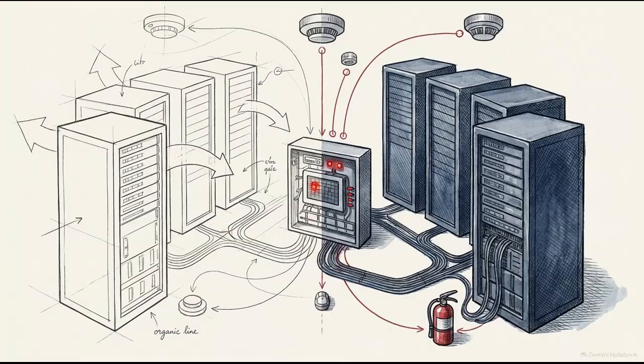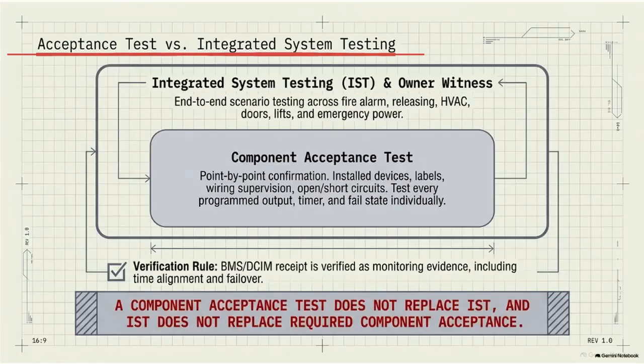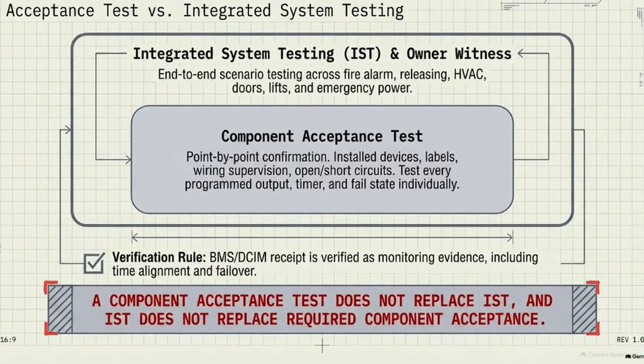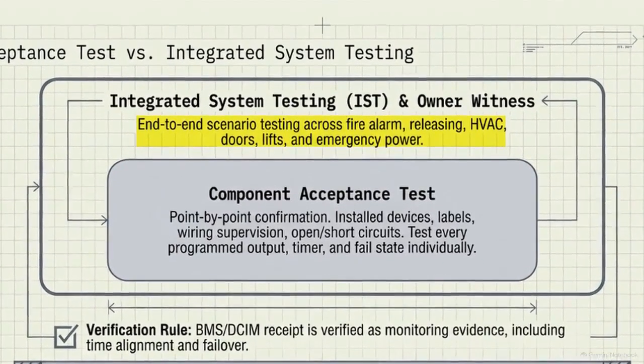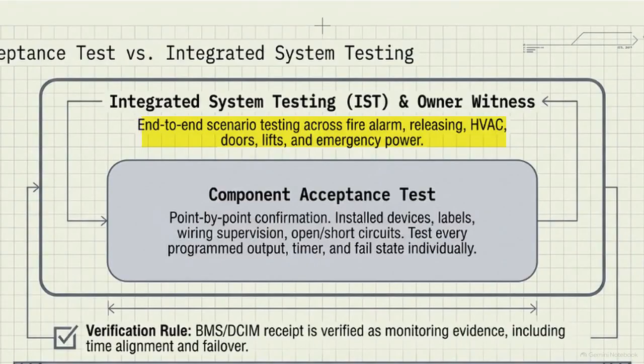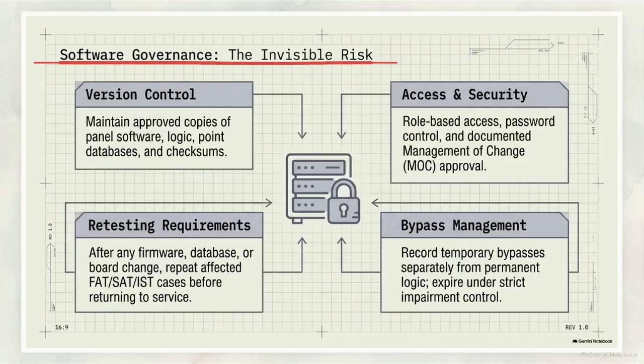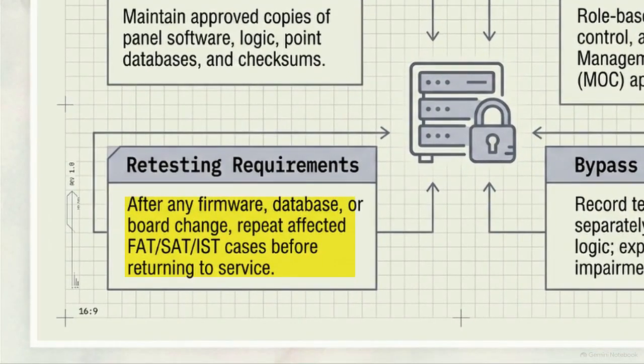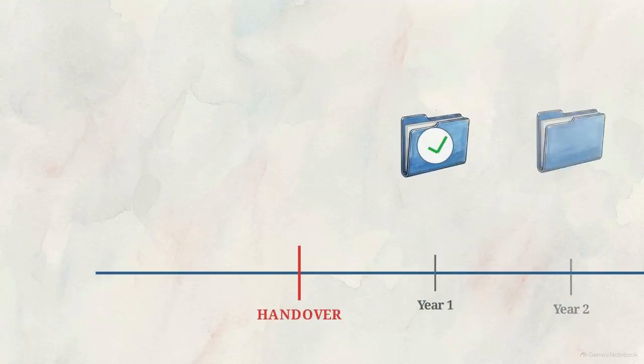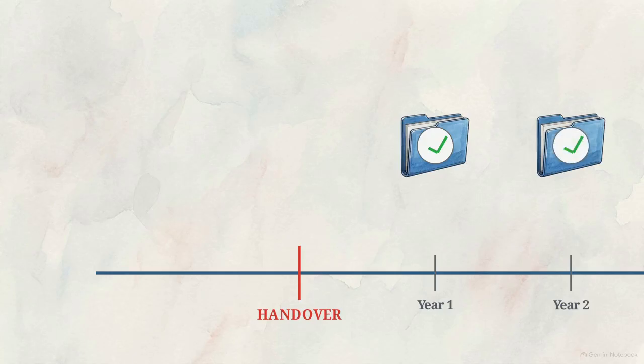An architecture is only defensible if it can be physically proven through rigorous field testing. There is a critical line between component acceptance tests and integrated system testing, or IST. A component test checking individual wires does not replace an IST. The IST verifies end-to-end interactions across HVAC, door releases, and emergency power. Unmanaged software updates represent an invisible risk over time. Any change to firmware or the system database mandates a repeat of the affected IST cases before the panel returns to service. Validation requires a continuous governance regime that survives for the life of the facility, long after the initial handover is complete.